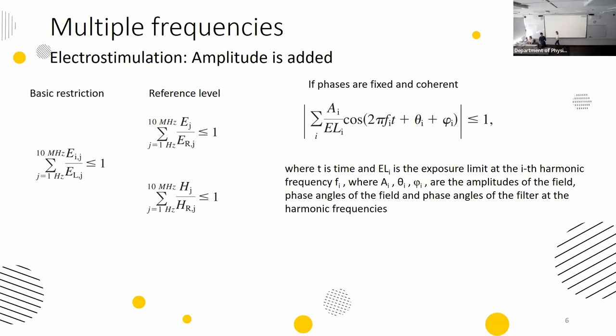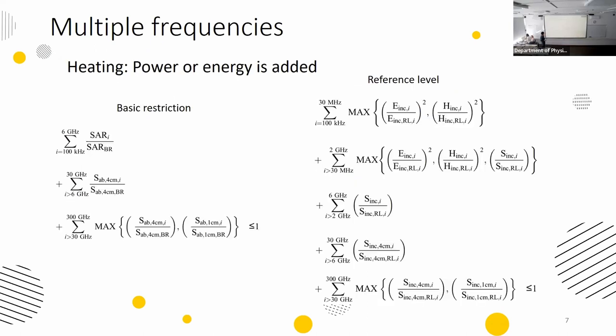This approach of adding spectral components is quite conservative because it assumes all spectral components are in phase. When you know the exact phases and the phase shift between components is constant and confirmed, you could apply a different formula and get lower combined results, making it easier to comply with the standard. For heating, since heating is proportional to power or energy, you need to add the square values of amplitude, or SAR itself, so you add powers.